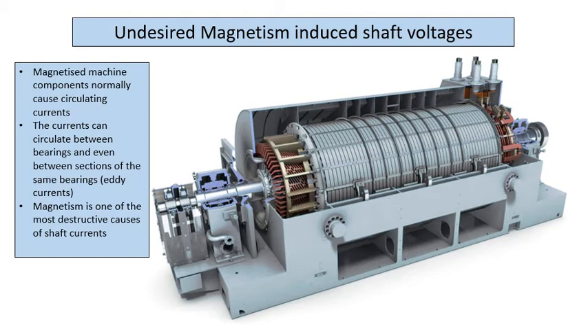You can go look that up on your own. This is the origin of homopolar DC shaft voltages. So if your bearing is magnetized here, and you've got a north there and a south there, for example, and your shaft spins, you get a Hall effect occurring, and you get a DC voltage across the shaft. It won't be AC. So if any of you have ever come across a DC shaft voltage, that's what it's caused by, as well as the phenomena that Stian mentioned.